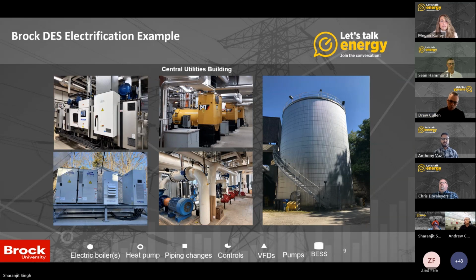Pre-DES electrification, we used our cogen plant, made up of four 2-megawatt Caterpillar 3516H gensets. Brock not only depends on the cogen for electricity generation, but prior to the electrification project, it was our primary source of heating for the campus. We're kind of a trigen, as we use that heat in the summer for absorption chilling, providing enough heat to produce 1,000 tons of cooling on campus in the summer months.